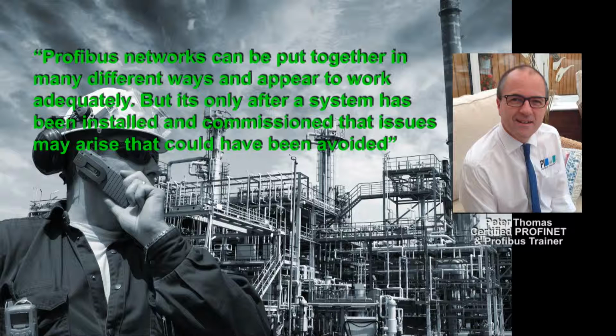And the kind of issues that I'm talking about here are things like maybe we want to do some diagnostics and we can't get onto the network. They haven't put a sufficient number of piggyback sockets there and in the correct place. Maybe they've broken the network down into several segments, which is fine, but then we come along and we find that in order to adequately test the network, we have to do a test on every segment, which then becomes time-consuming. And maybe if we designed it in a different way, we could have done it with fewer segments.